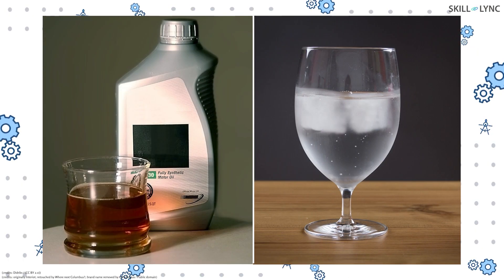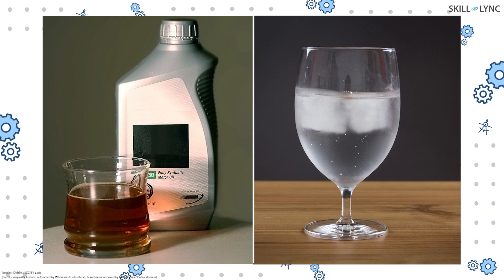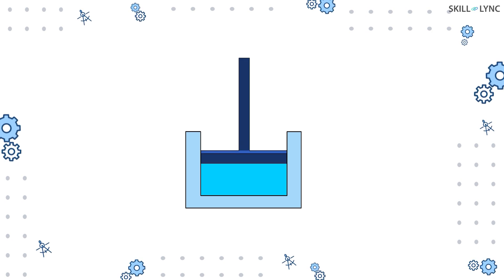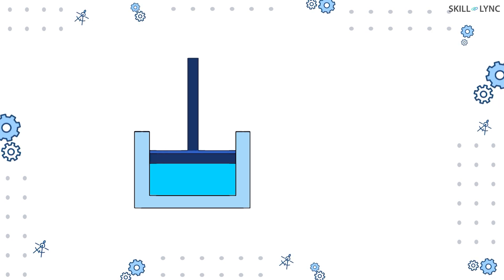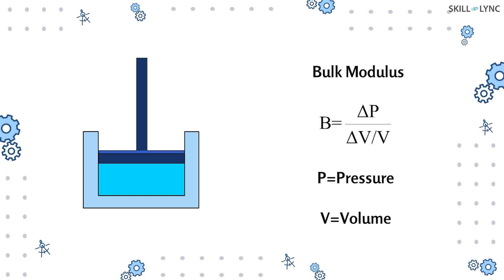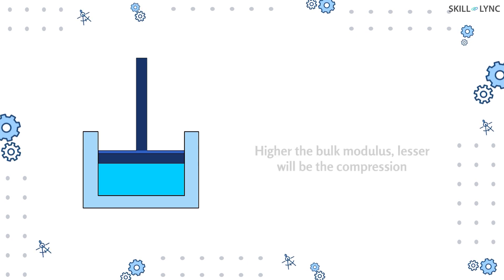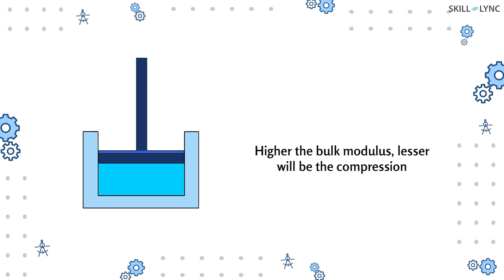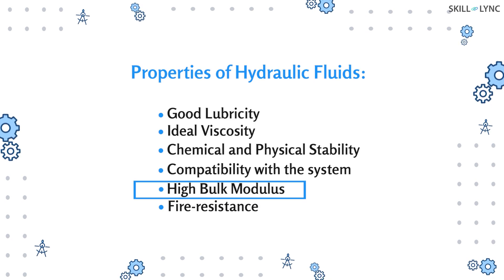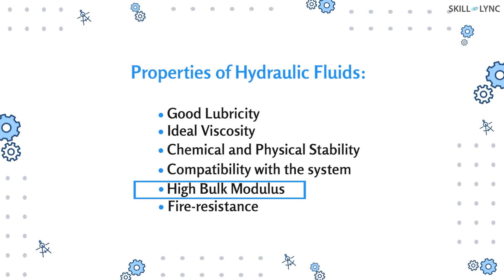As we have seen in our previous videos on fluid power, most liquids like oil or water are considered incompressible, although in practice all materials are compressible to a certain extent. The bulk modulus of a liquid is the measure of compression with an increase in pressure. A material with high bulk modulus will undergo lesser compression as compared to a material with low bulk modulus. Therefore, the hydraulic fluid must have a high bulk modulus for proper working.